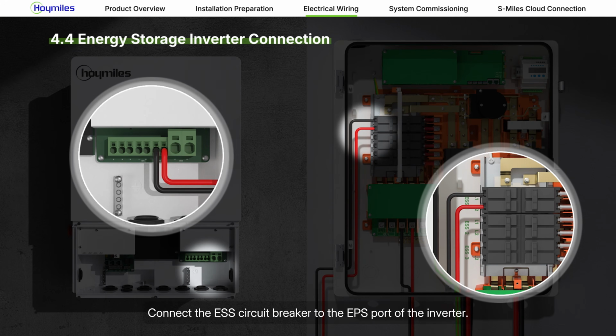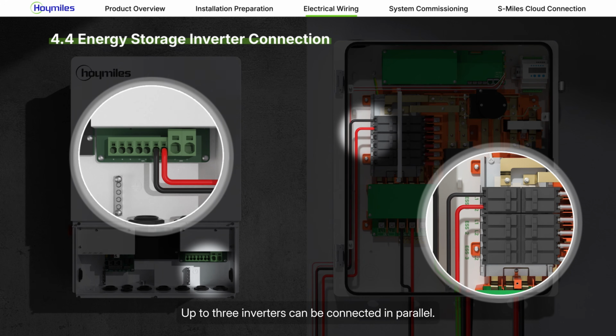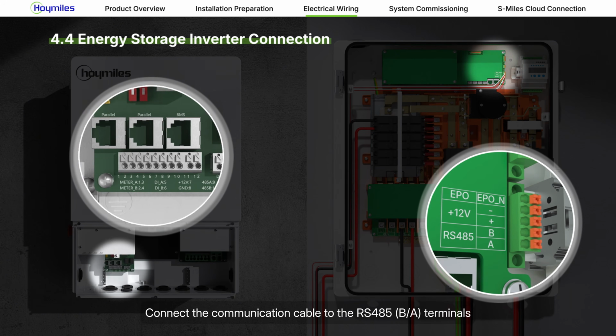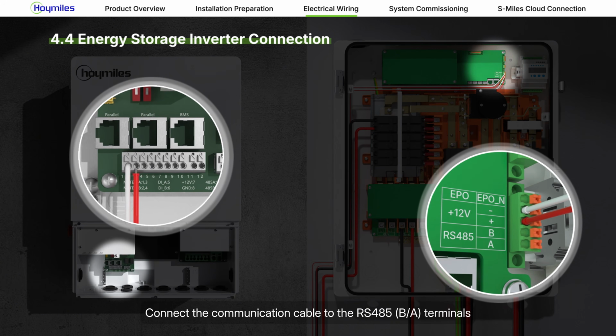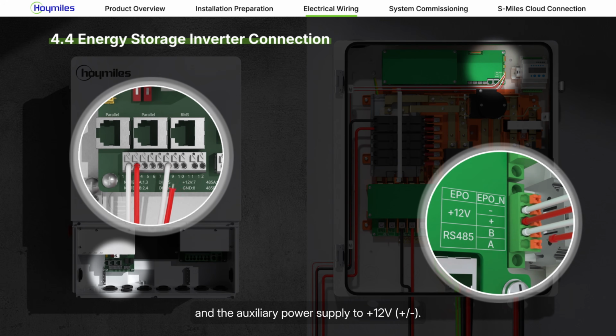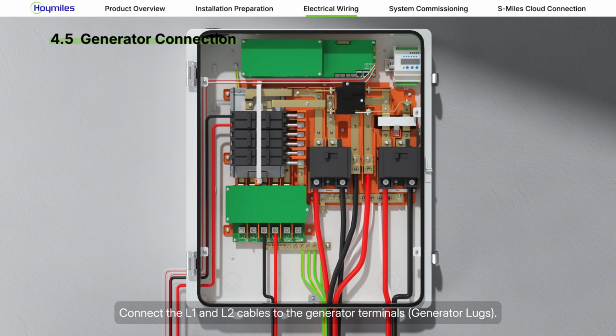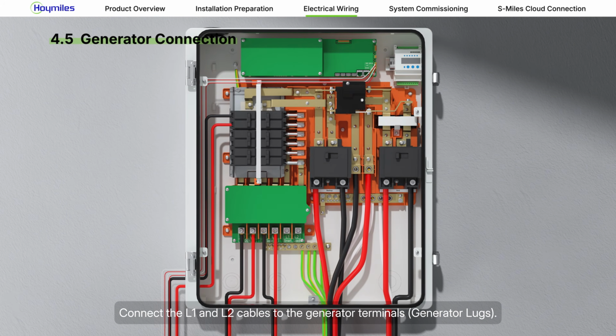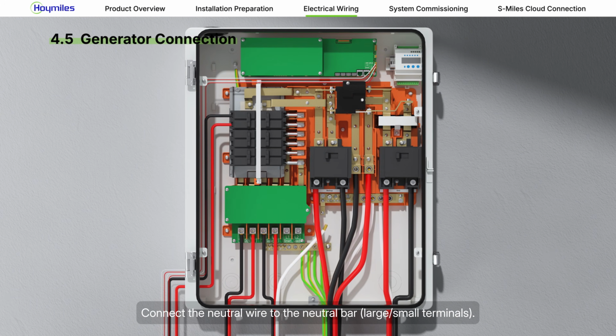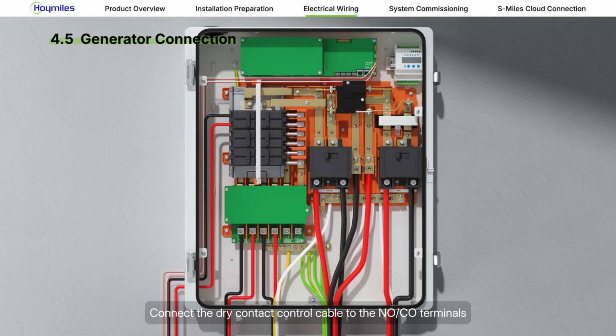Connect the ESS circuit breaker to the EPS port of the inverter. Up to 3 inverters can be connected in parallel. Connect the communication cable to the RS-485 terminals and the auxiliary power supply to 12 volts. Connect the L1 and L2 cables to the generator terminals. Connect the neutral wire to the neutral bar. Connect the ground wire to the grounding bar. Connect the dry contact control cable to the NO or COM terminals and the CT cable to CT1, CT2.